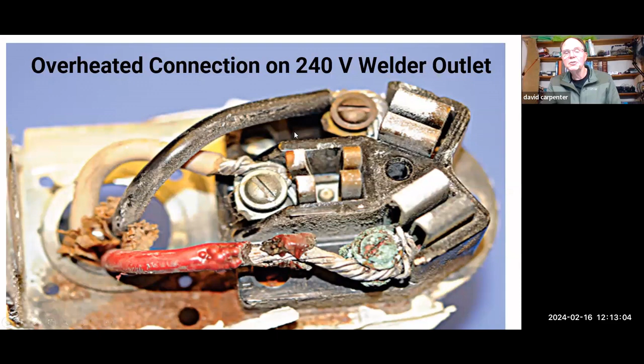This is a welder, unfortunately I see this quite often. This is just a violation of the way it's wired up. As you can see, you've got more heat on one leg than the other, and this is a problem. This person did have a fire that started through here. They were very fortunate it didn't go very far, but they did have a fire from this one.